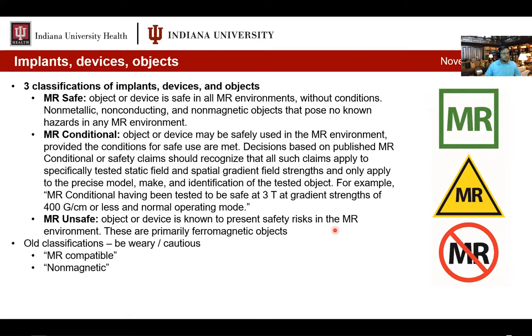Old classifications that you should be wary of and should not use anymore are MR compatible, which is not an approved term by the FDA anymore, and non-magnetic. A lot of our fire extinguishers say non-magnetic. That does not make them MR safe, unfortunately. So these 2 terms are not approved by the FDA anymore. One other fourth term that's floating out there that I use a lot is non-MR conditional. That is felt to be the same as MR safe, and it is actually a term that is used explicitly by the ACR, but they prefer that we use these three specifications going forward. So try to use MR safe, MR conditional, or MR unsafe as much as possible to be as clear as possible.